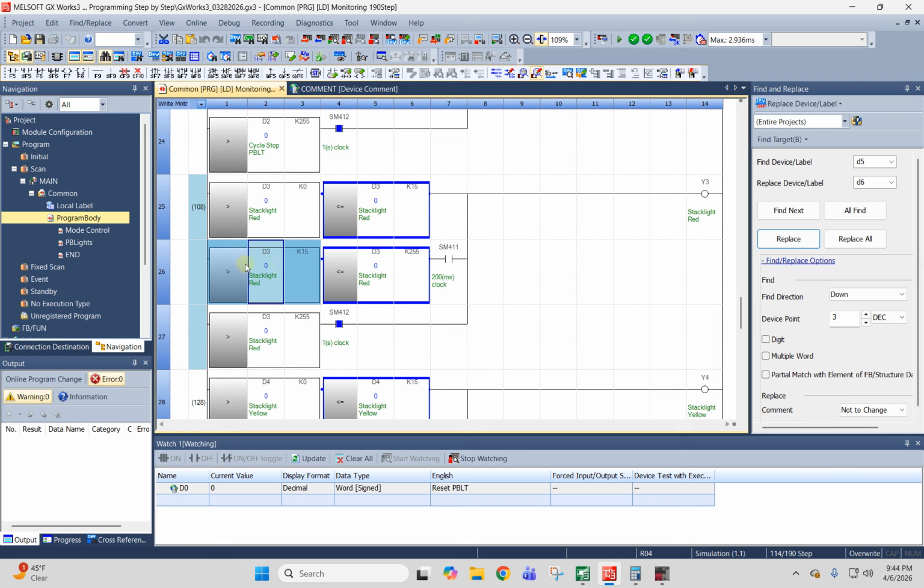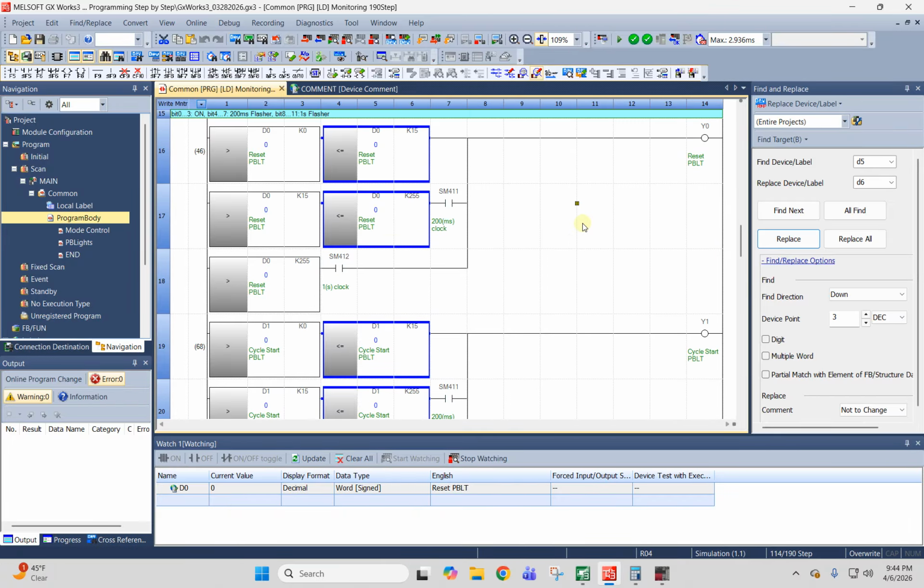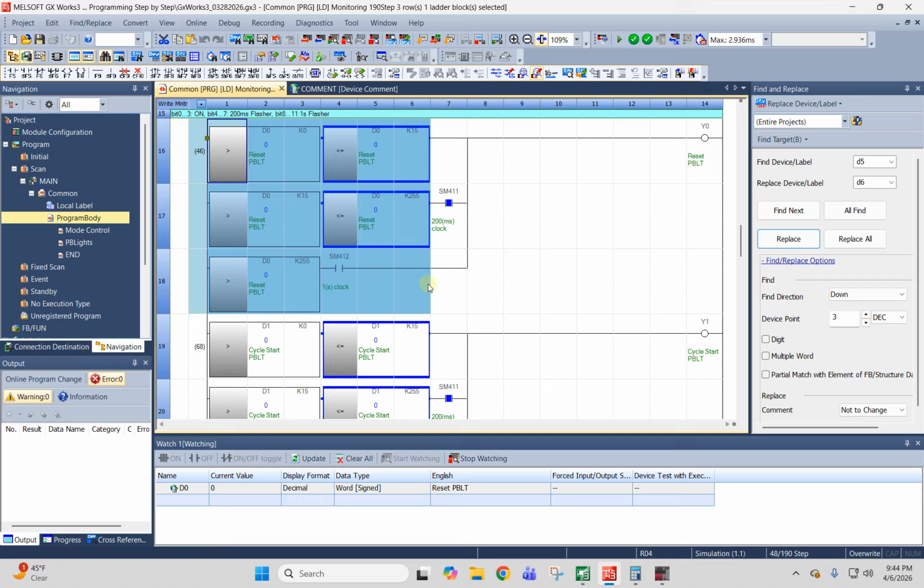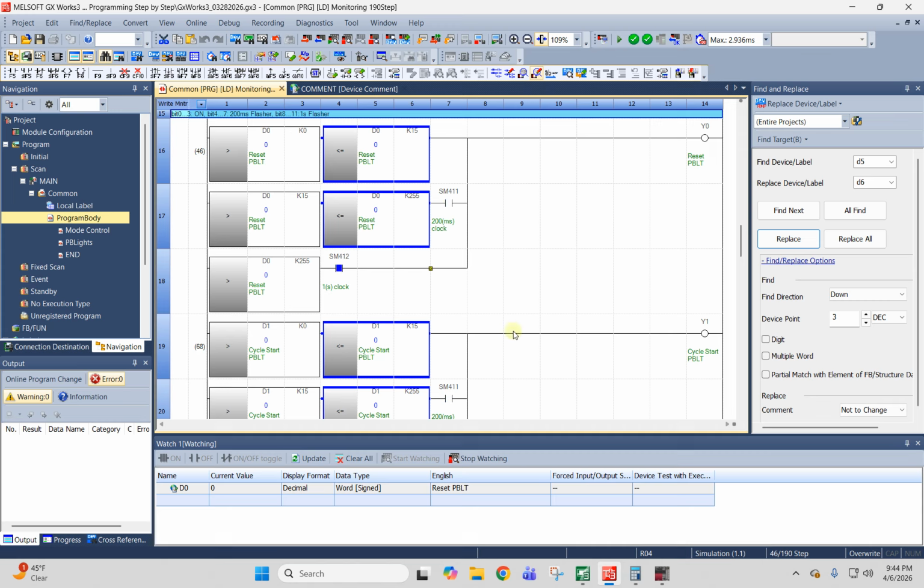And this gives you the flexibility of using these D's anywhere in the program, and you don't have to basically remember what's the M memory to set and reset and things of that nature. If it's something, you can make it flash. Now also, you don't have to have these conditions. You can basically do a not equal 0 and turn the light on. That's the simplest way to do it. I like this because it gives a little bit more flexibility, but you have to remember the bits break down and you can use it more.